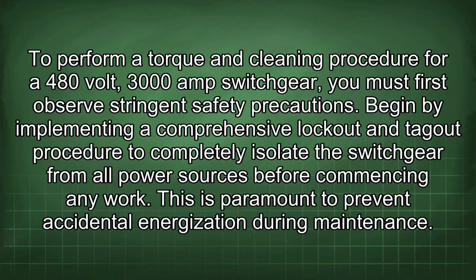To perform a torque and cleaning procedure for a 480-volt, 3000 amp switchgear, you must first observe stringent safety precautions. Begin by implementing a comprehensive lockout and tagout procedure to completely isolate the switchgear from all power sources before commencing any work. This is paramount to prevent accidental energization during maintenance.